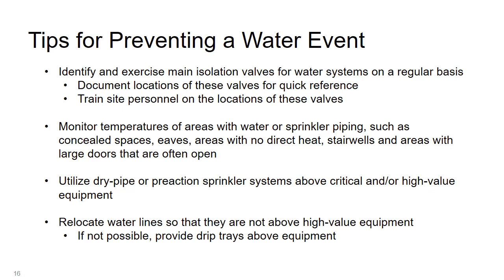The bottom 2 points here are worth considering if there are any major changes made to a facility that involve high-value equipment. By reducing water present above this equipment, it directly reduces the possibility of a leak affecting the equipment if a failure were to occur.